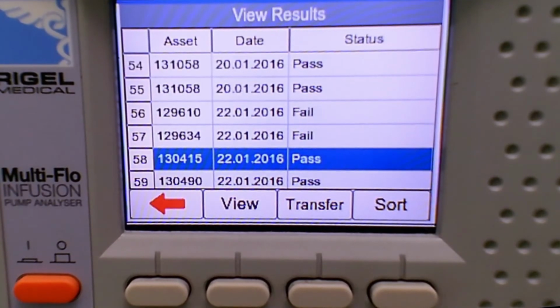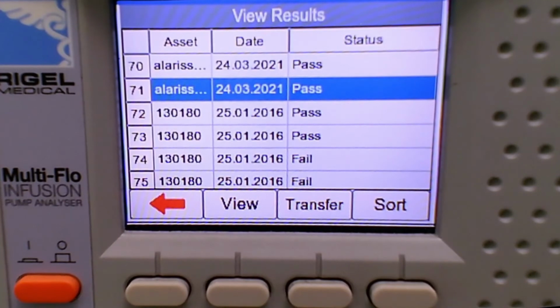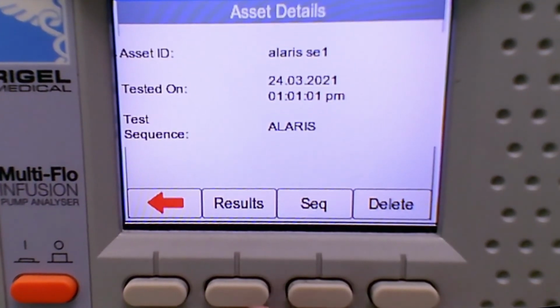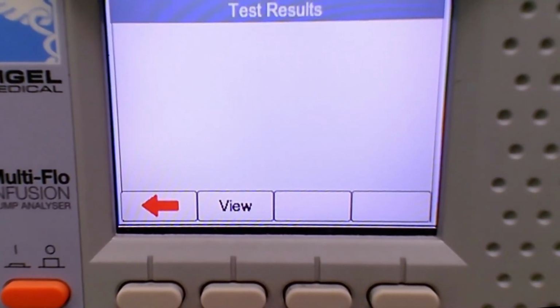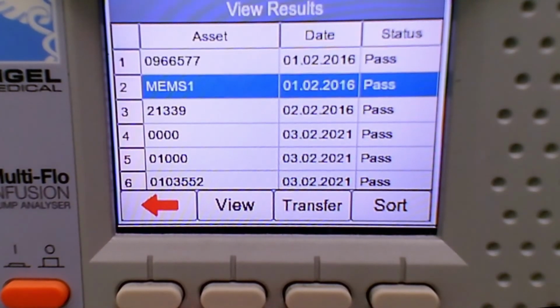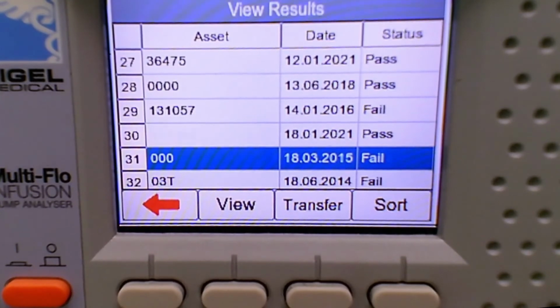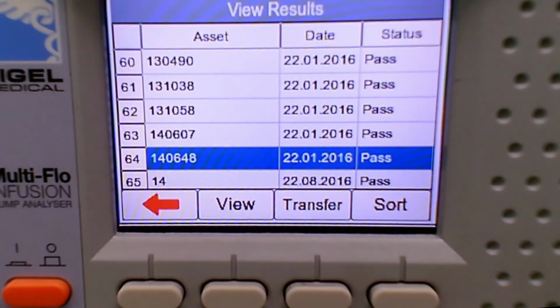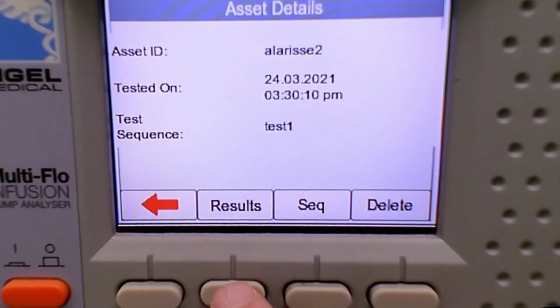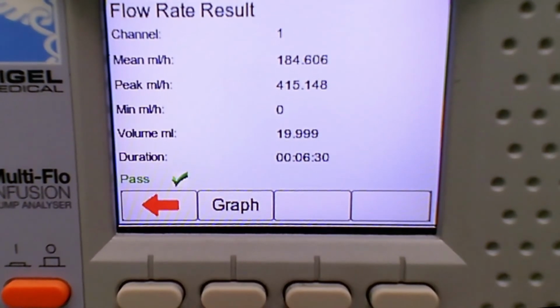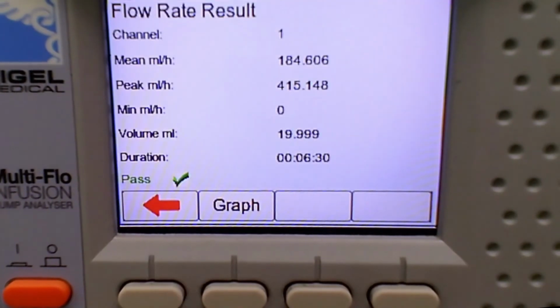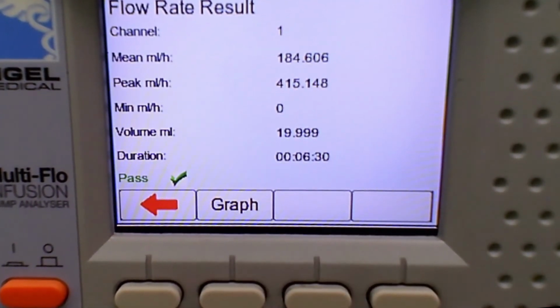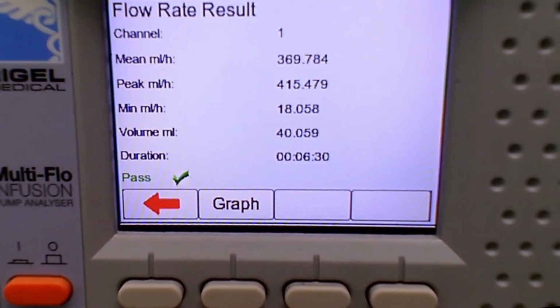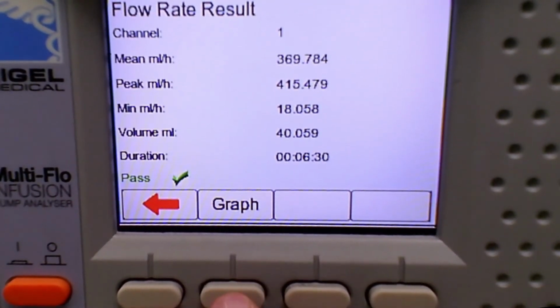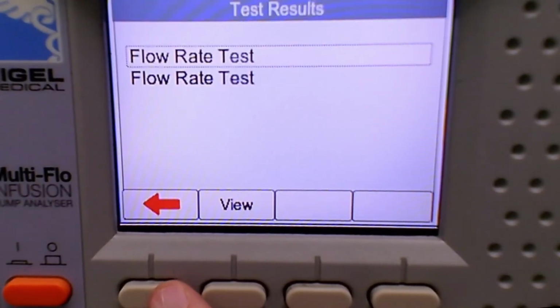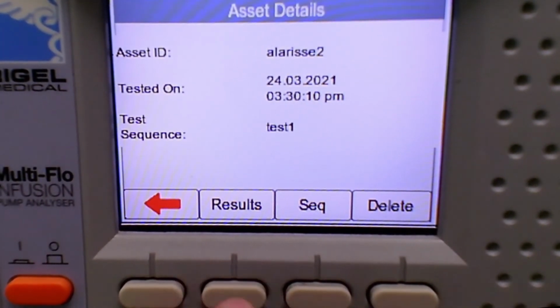Okay, so I'll just cycle through these results to try and find the one we're after. Is it that one? No, it's alarisse2, I think. Quite a few asset IDs on here, so it takes a bit of time cycling through. See where the benefits of Med-eBase come in. Okay, so we've got our two flow rate tests. We've got our volume, 19.99. We've got the graph showing the flow rate. So well within specification for this, and even for the volume on there. I think we kept the flow rate going for the 40 ml one just slightly at the end there, so that might be why it's reading over. We'll have to redo that test, but it's still within specification, even after the time's elapsed.